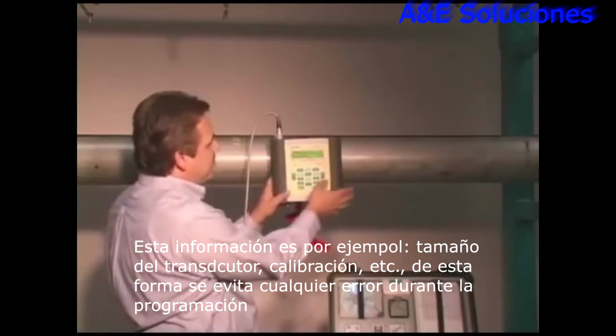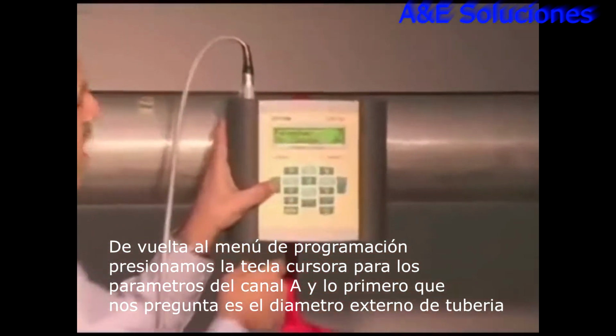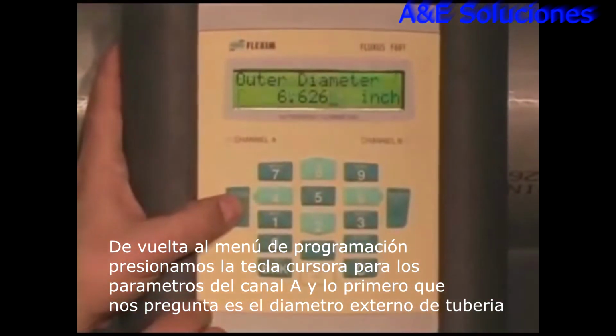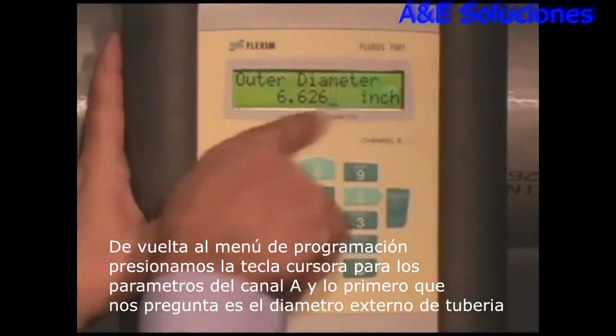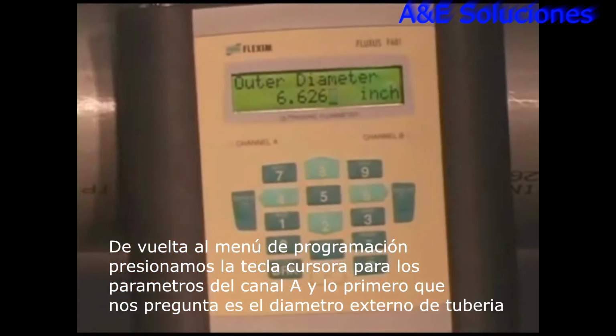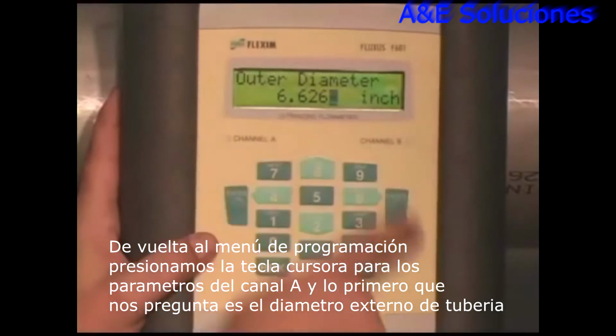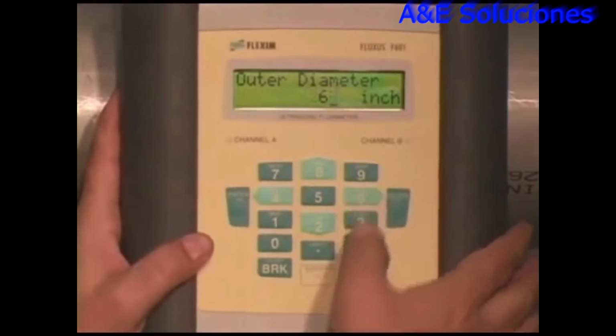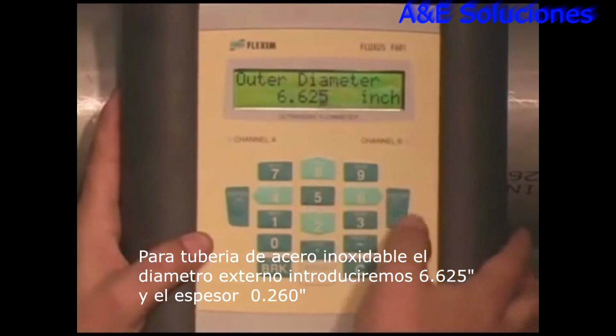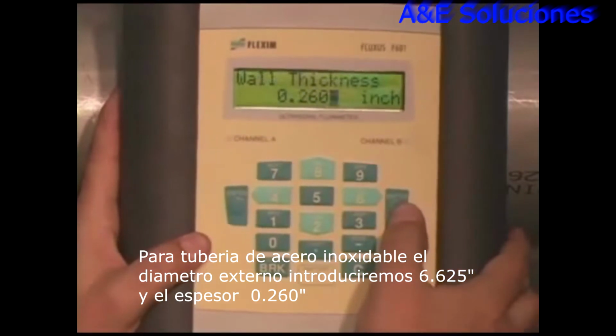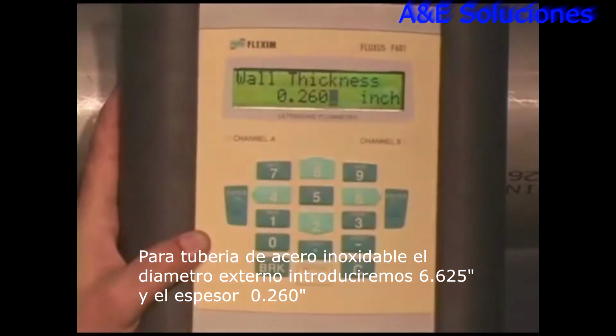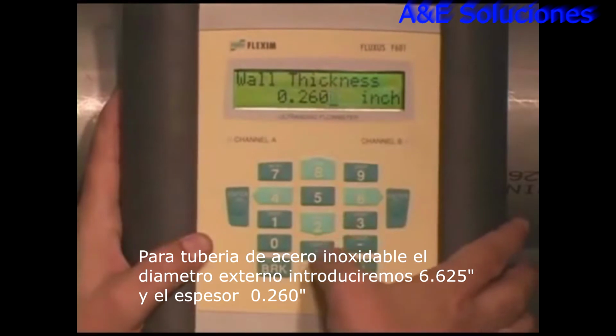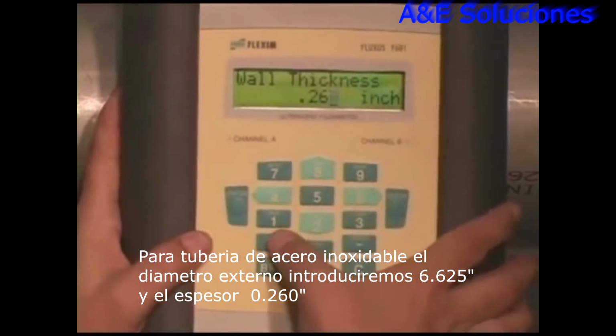So back to the parameters menu. We hit the enter key, parameter for channel A. And the first thing it asks now is what is the outer diameter of the pipe. Now you can see that we've already cheated on this one, because this is a 6-inch pipe, but I'm going to enter that pipe dimension in for you. We just punch in 6.625 and press enter. Then we punch in the pipe wall thickness. This happens to be a 0.260 pipe wall.